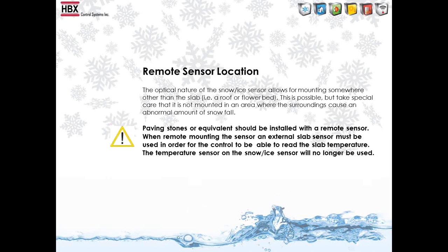With our optical sensor, you can remote mount the sensor on a roof or in a flower bed. With that, you will need to install the included thermistor in the slab you are monitoring, as you need to know the temperature of the slab for the system to function properly. We suggest that when mounting the optical sensor remotely, you install the external thermistor instead of relying on the temperature sensor within the optical sensor.